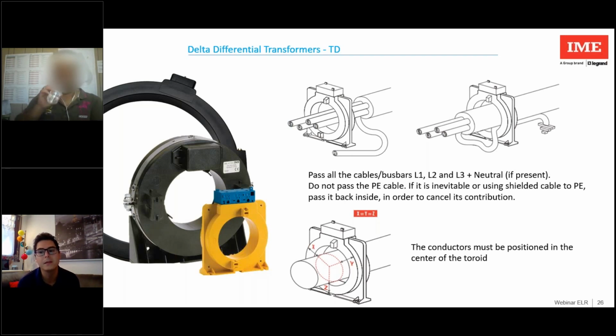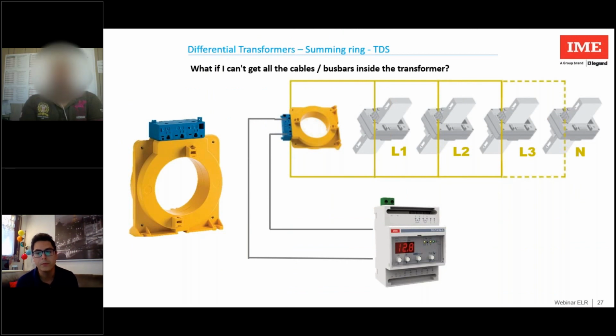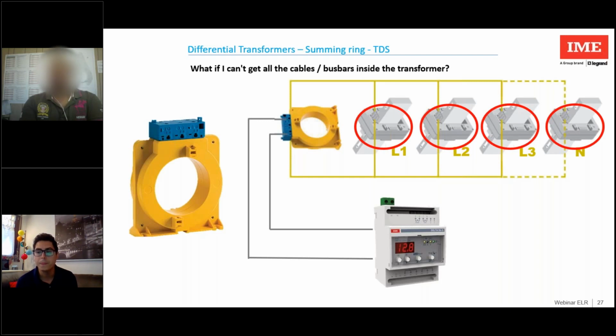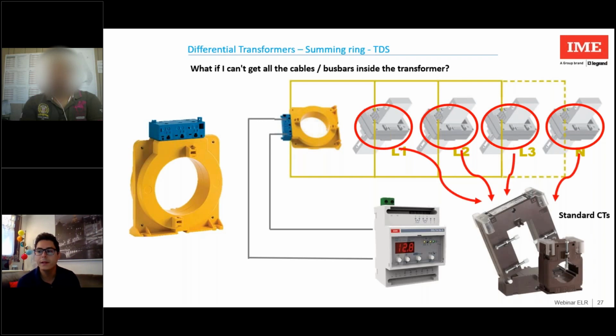What if I can't embrace all this cable, all this busbar, for example because they are far away? Here, a summation toroid comes to our help. The installation is done by connecting normal CTs, the standard ones shown in the last webinar, with the rated current closest to the maximum current that could pass, connected in parallel all together, and going to the added toroid. This toroid will connect to the relay.